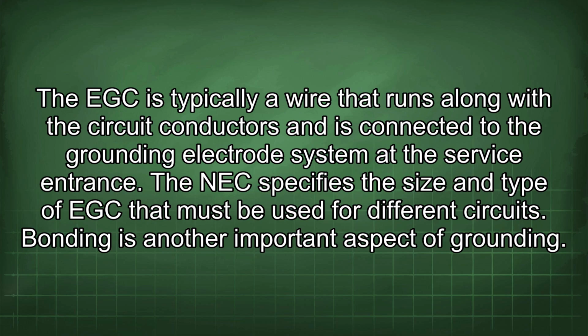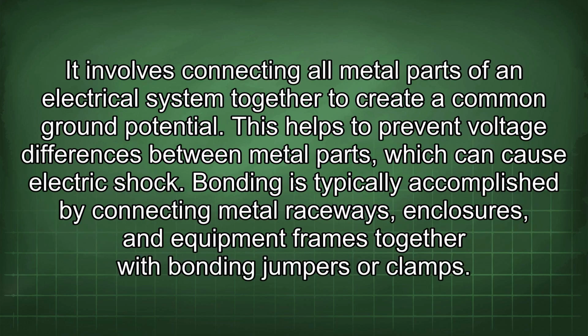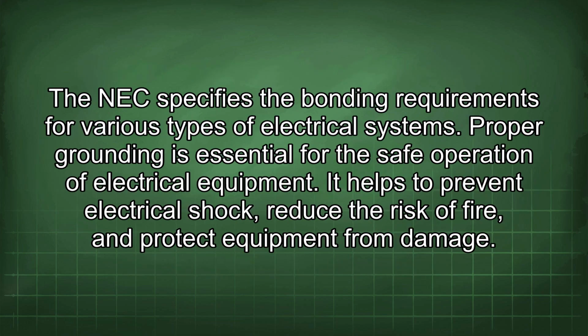Bonding is another important aspect of grounding. It involves connecting all metal parts of an electrical system together to create a common ground potential. This helps to prevent voltage differences between metal parts, which can cause electric shock. Bonding is typically accomplished by connecting metal raceways, enclosures, and equipment frames together with bonding jumpers or clamps. The NEC specifies the bonding requirements for various types of electrical systems.